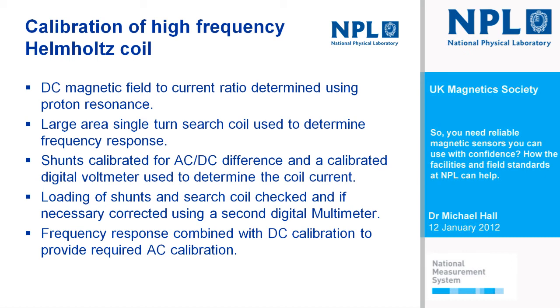So as we go up in frequency, the coil constant increases with frequency, and that is because we are measuring the current outside of the coil system, and the current which is actually in the windings is larger because of the distributed capacitances across the windings. So therefore the coil constant apparently increases as we go up in frequency.